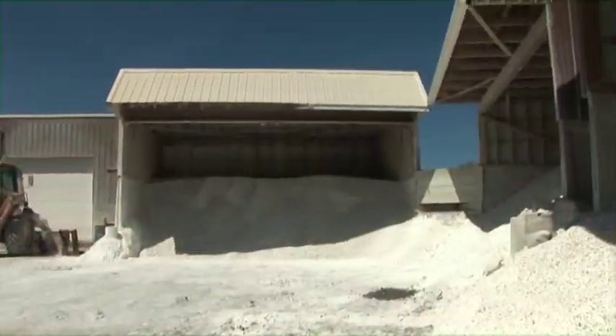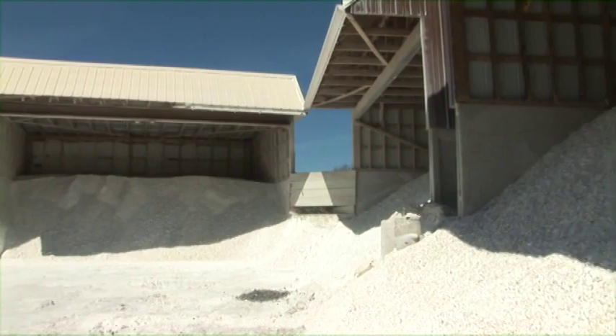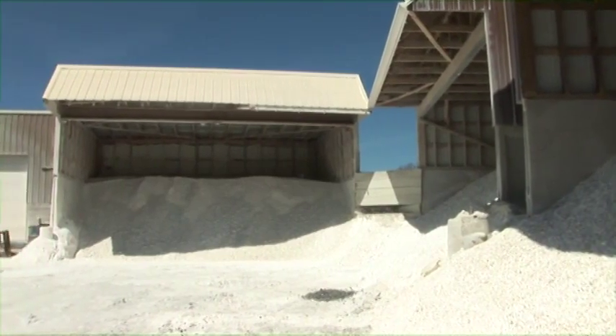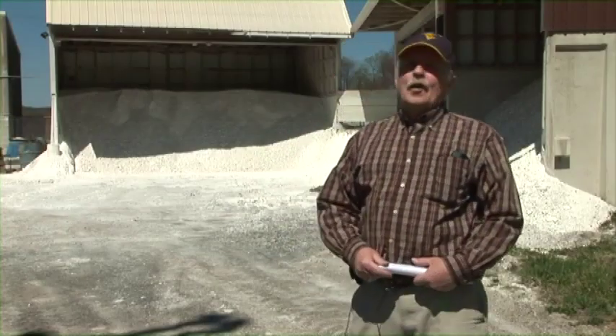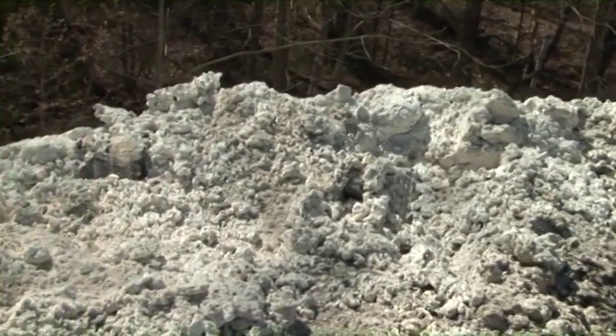For the lime that we use to treat the water, we get this material from Graymont Industries, which is at Pleasant Gap near State College. When they're making hydrated lime, they cook the limestone, and when they clean the kilns out, we get the material, which they can't use. They don't like us to call it a waste material, so we call it lime scrapple. It costs like $9.75 a ton, and if we used what most plants use, the material costs like $150 a ton. We use about 600 tons a year.